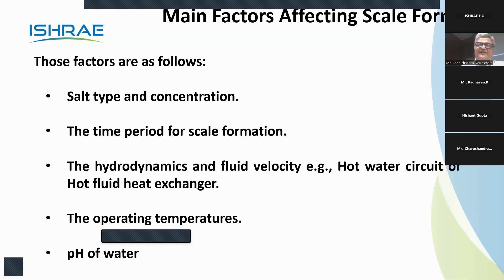Fouling deposits increase directly with the concentration of calcium sulfate. The reason I have taken calcium sulfate as an example is that if calcium carbonate is higher in water, we add a small amount of H2SO4, sulfuric acid, into the water to turn calcium carbonate into calcium sulfate, because calcium sulfate has better solubility and remains better in water, meaning it will not form scales so much.